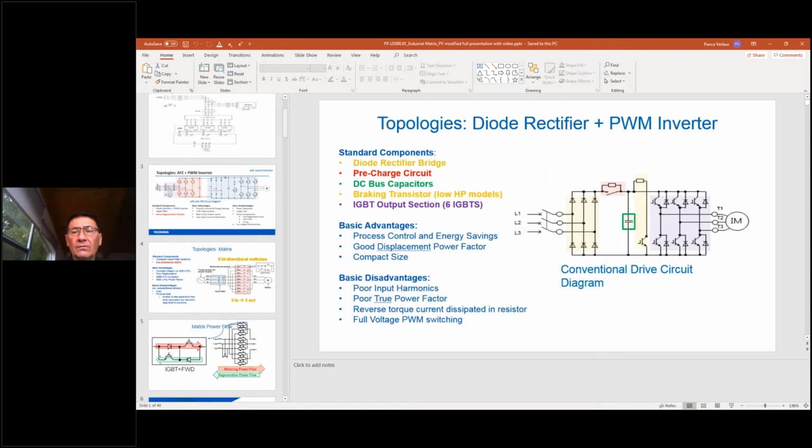Grundfos and Franklin have come out stating that they require filters on the output of the standard 6-pulse constant voltage DC bus 6-transistor inverter bridge VFD. Probably 90-95% of what's out in the market right now. This is because they have two issues with the VFD as opposed to sine wave power coming directly from the utility to their submersible pump via a contactor.